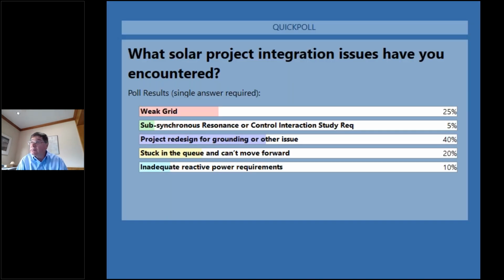We've got solar projects integration issues encountered. It looks like 40% say project redesign for grounding or other issue. 25% say weak grid. 20% say stuck in the queue, can't move forward. And 10% say inadequate reactive power requirements, and 5% say subsynchronous resonance or control interaction study requirement.